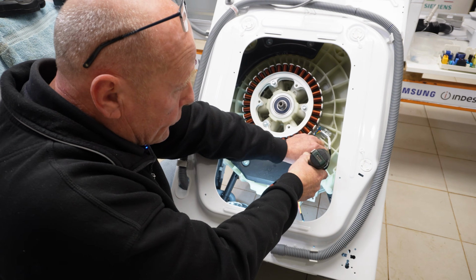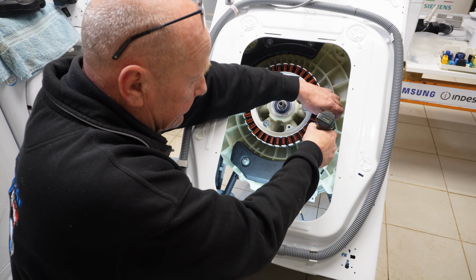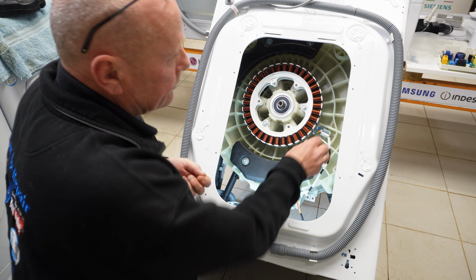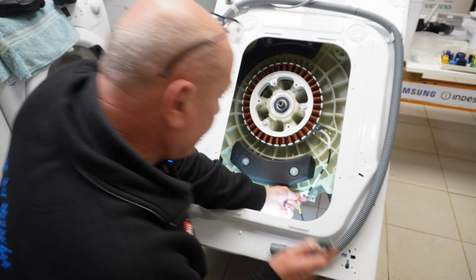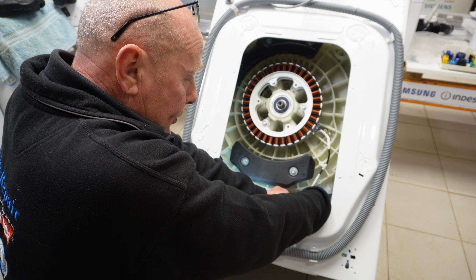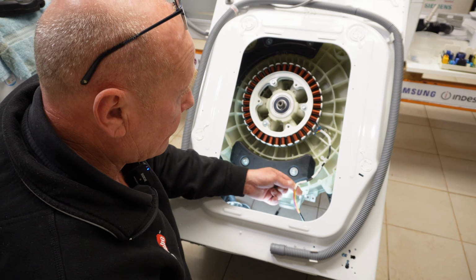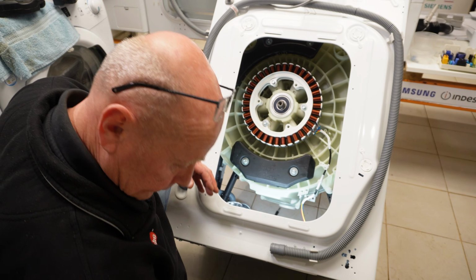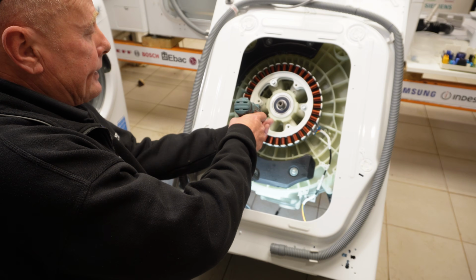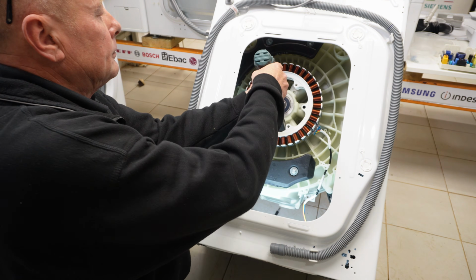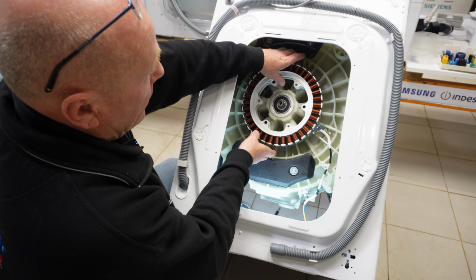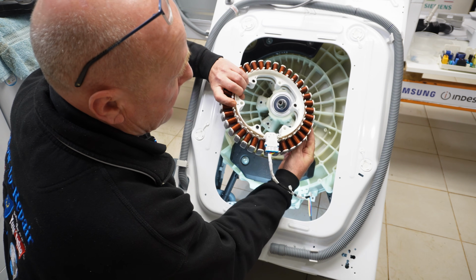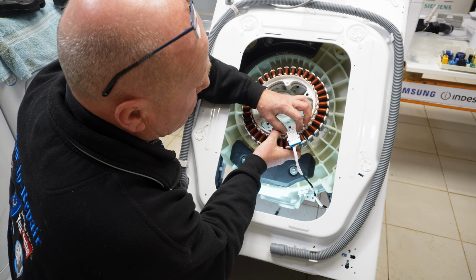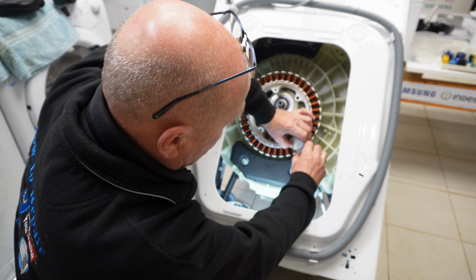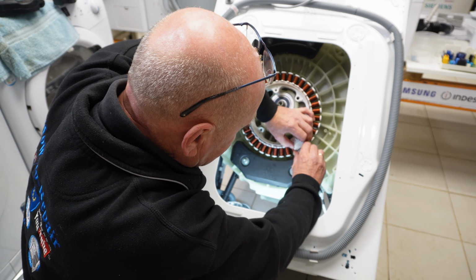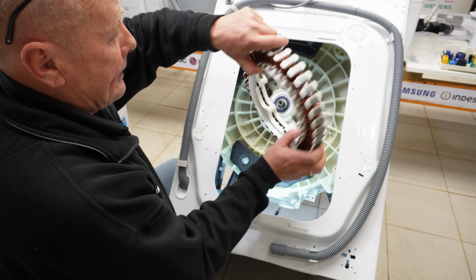First we need to undo these 2 screws that hold the cabling in place, and also cut away the cable ties that hold the harness in place. That's all loose now. We can now undo the stator. The motor will come away, and then you're able to flip it over, press down these pins, which are sometimes tricky to get off. Make sure you don't damage the motor. And the plug will come away, and that is the motor.